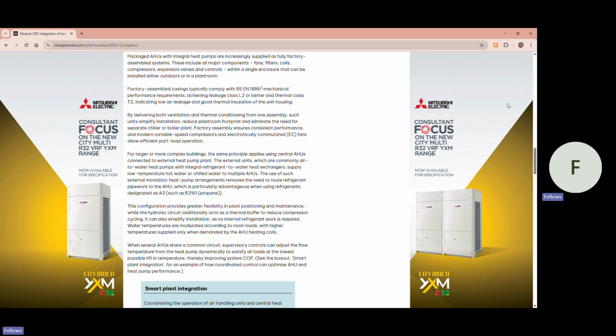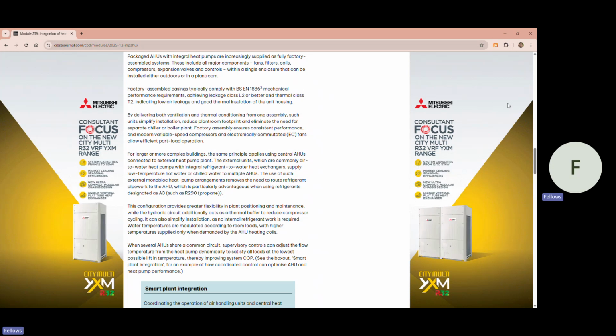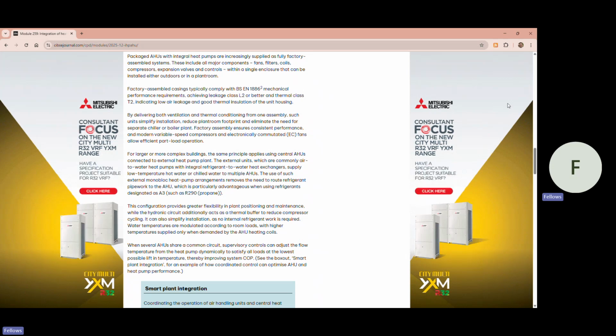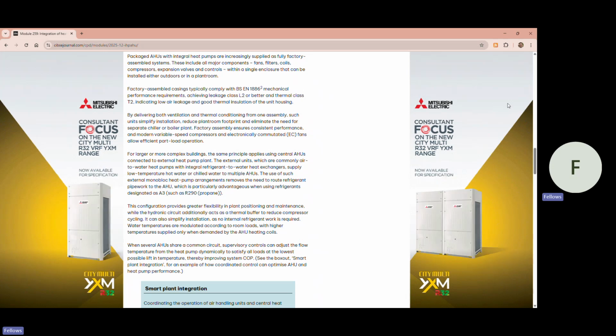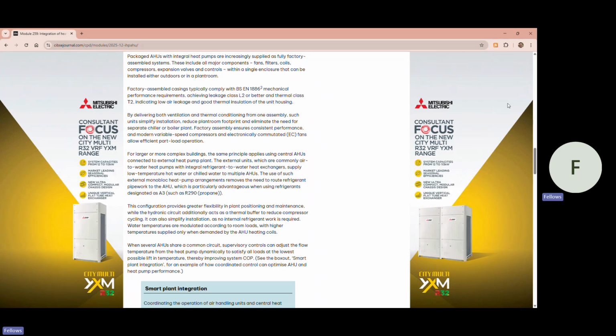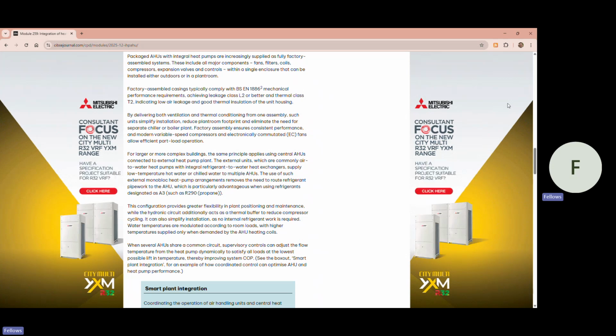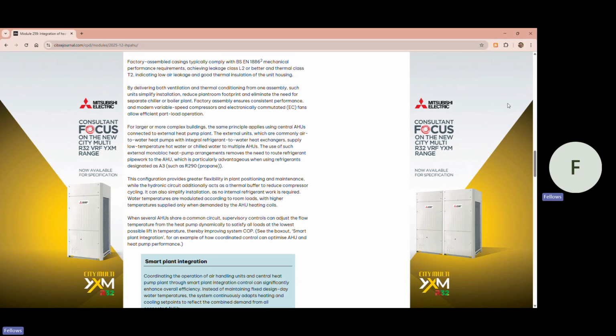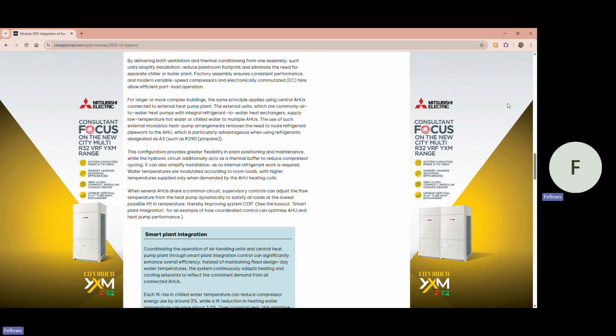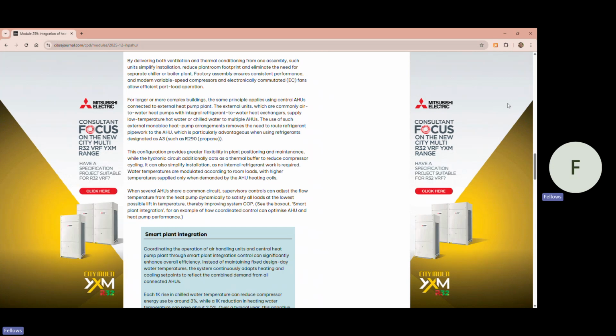The external units, which are commonly air-to-water heat pumps with integral refrigerant-to-water heat exchangers, supply low-temperature hot water or chilled water to multiple AHUs. The use of such external monoblock heat pump arrangements removes the need to route refrigerant pipework to the AHU, which is particularly advantageous when using refrigerants designated as A3, such as R290 or propane. This configuration provides greater flexibility in plant positioning and maintenance, while the hydronic circuit additionally acts as a thermal buffer to reduce compressor cycling. It can also simplify installation, as no internal refrigerant work is required.